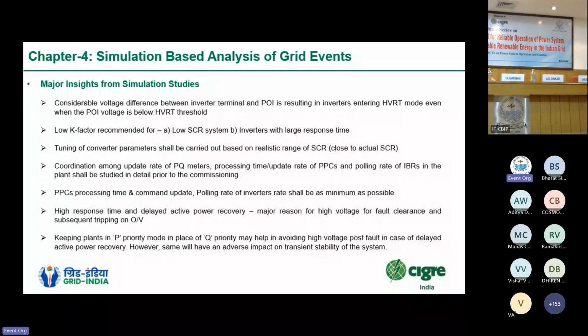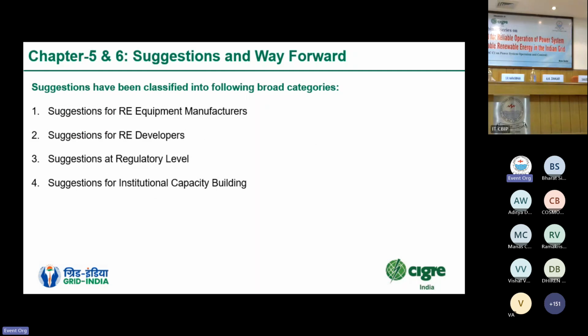So based on the simulation studies and results, it was concluded that the inverter should be able to take the commands of the PPCs at a very high rate. Again, high response time and delayed active power recovery in the LVRT curve: we can easily see that a very large response time may lead to the plant showing undesirable behavior during the low voltage ride through curve. So this was also identified as one of the reasons. And again, based on the simulation studies, feedback would be given on the P priority and Q priority modes based on the system strength. Chapters 5 and 6 of the report cover the details about suggestions and the way forward. Different sets of suggestions for different entities have been mentioned, so all the stakeholders have been given certain suggestions.